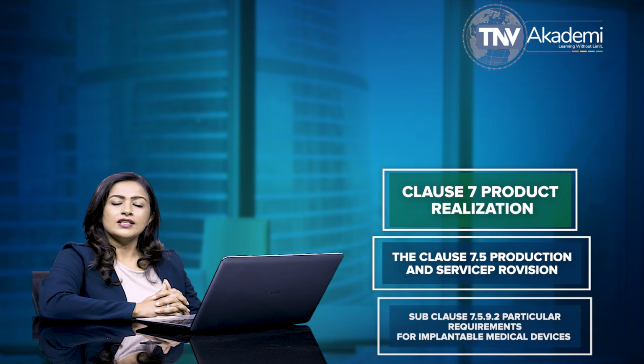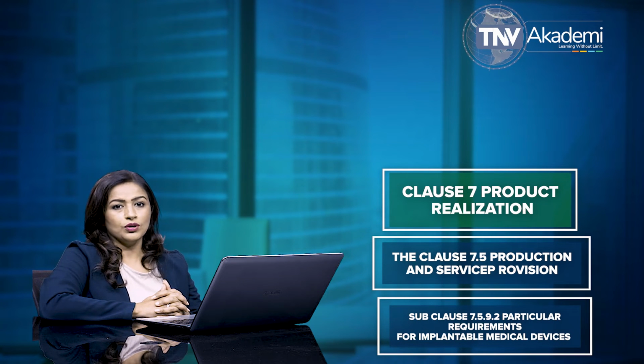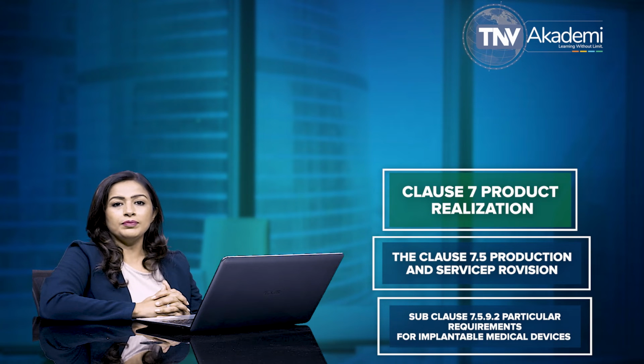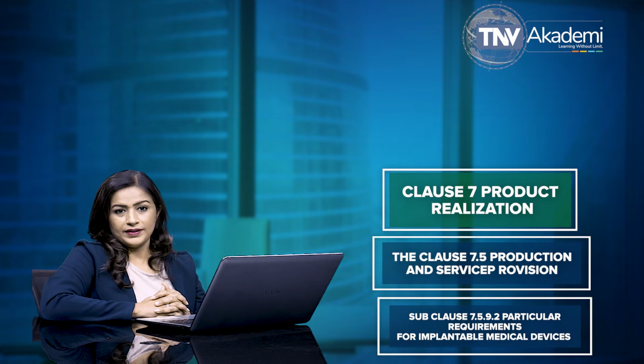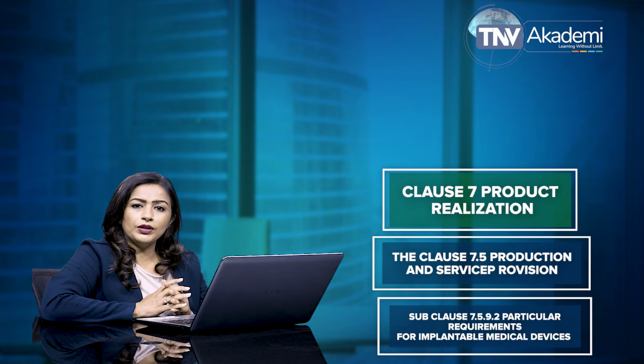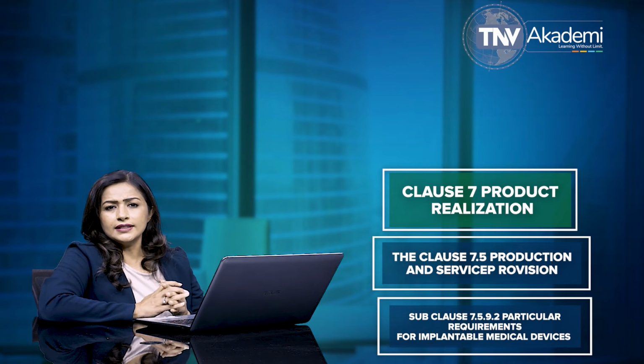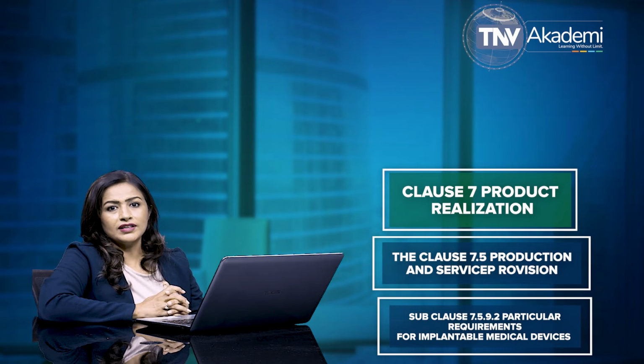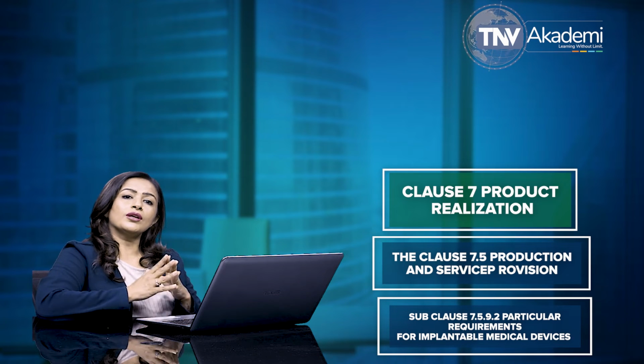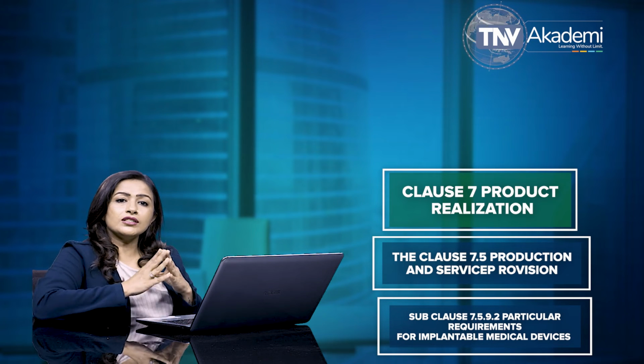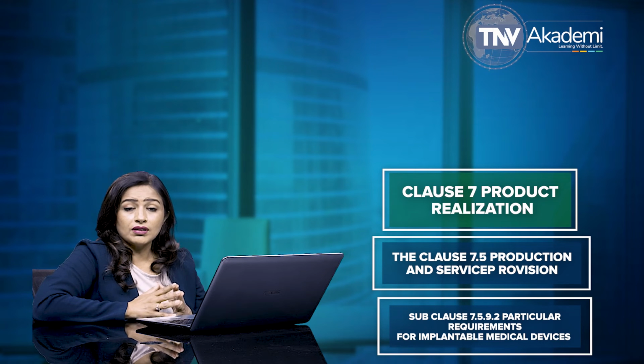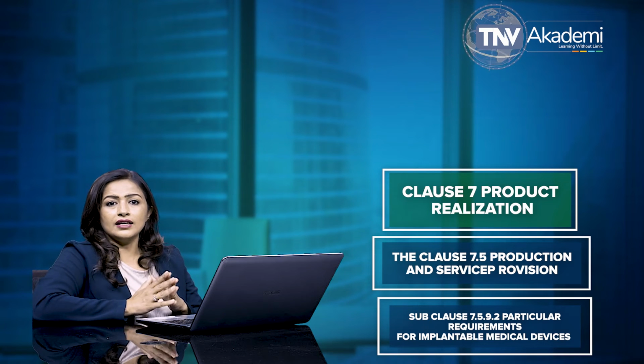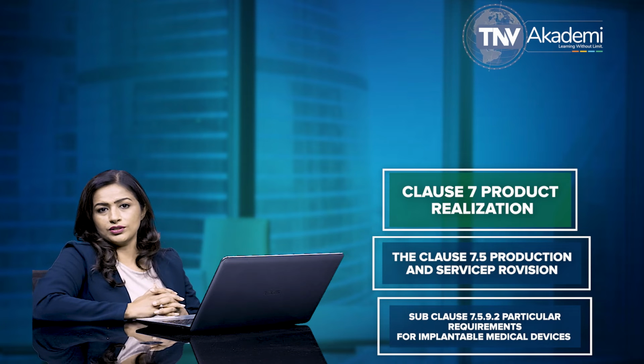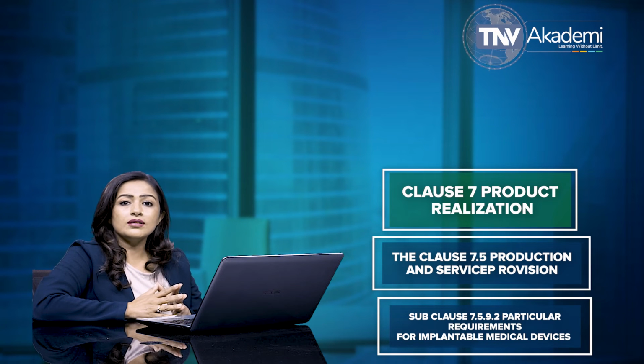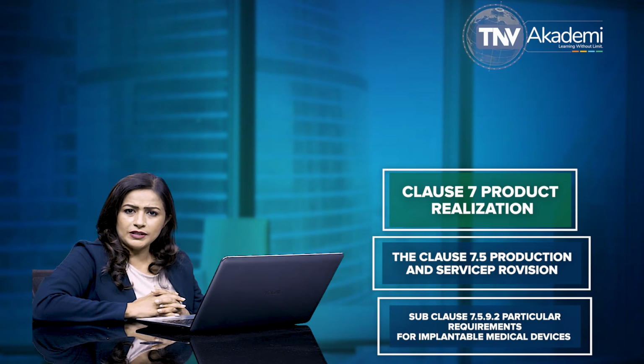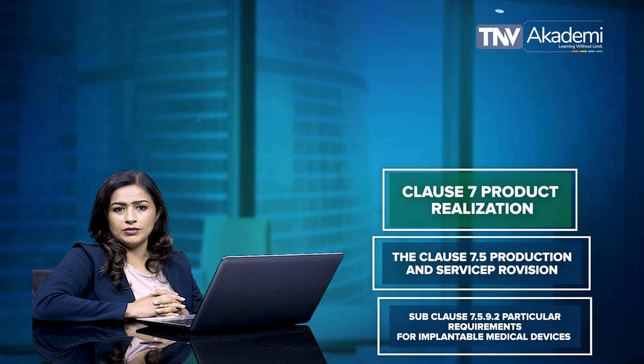Coming to subclause 7.5.9.2, particular requirements for implantable medical devices. This subclause 7.5.9.2 of ISO 13485 states that the records required for traceability must include records of components, materials, and conditions for the work environment used, if these could cause the medical device not to satisfy its specified safety and performance requirements.